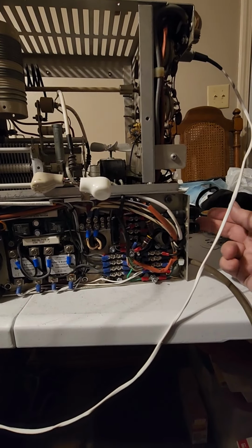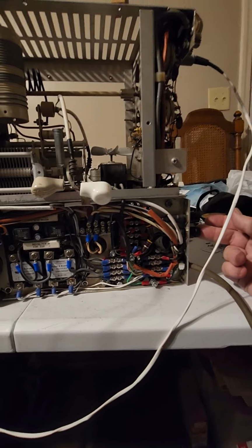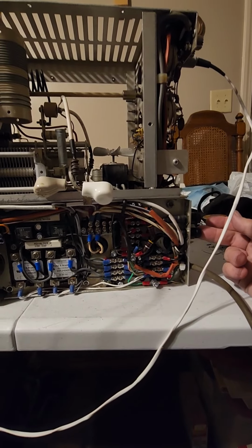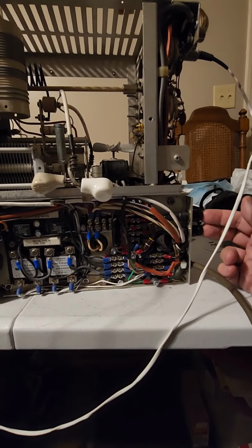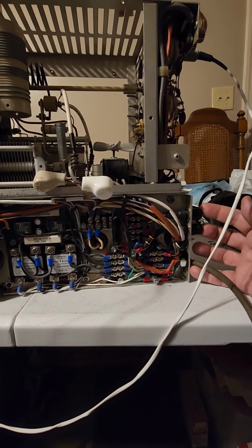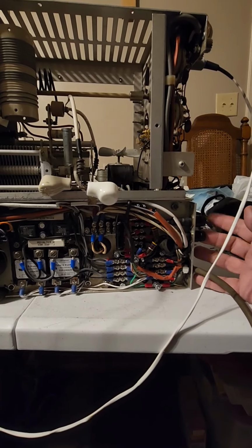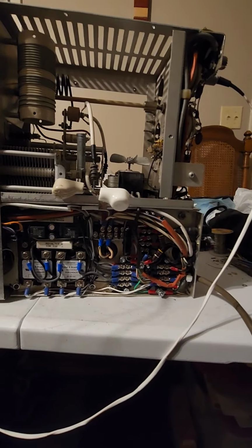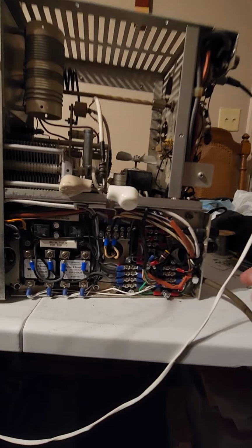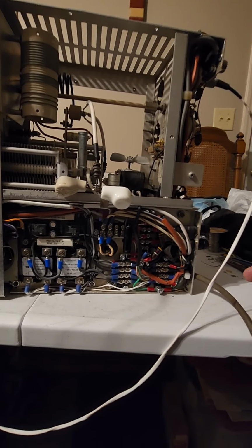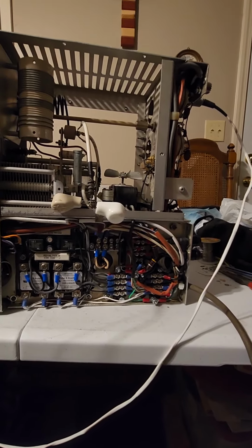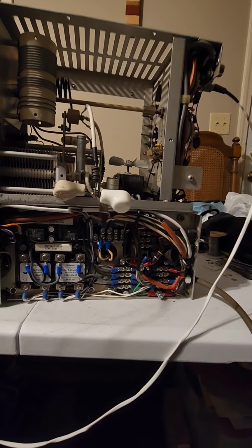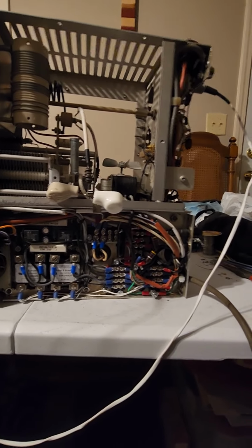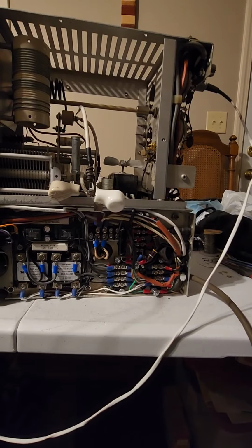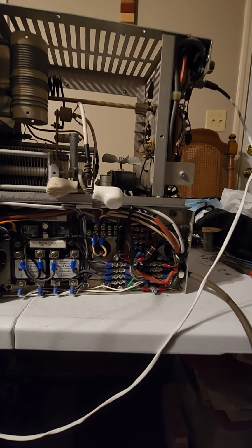That was with the cross setup. They tied the fuses together on the 120 system, and they ran separate lines on a 240 system because there are two separate primary windings, both 120 volts. If you remember from your electrical days, two windings in parallel are used for 120, and two windings in series are used for 240, with the center between the two as a neutral.